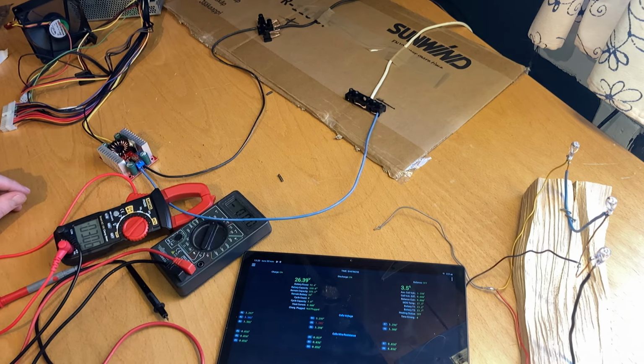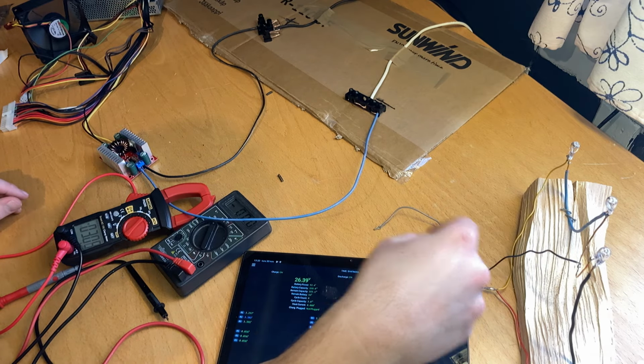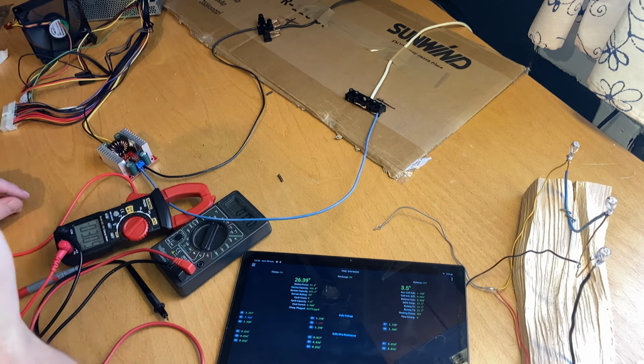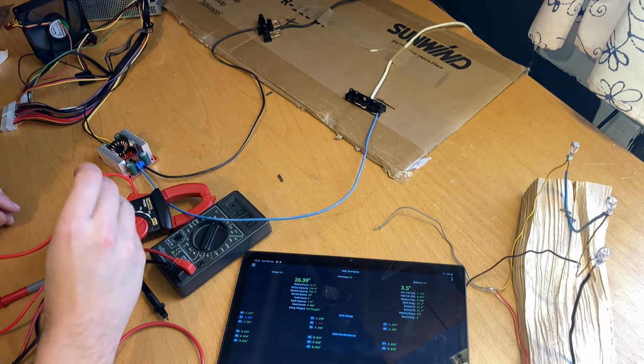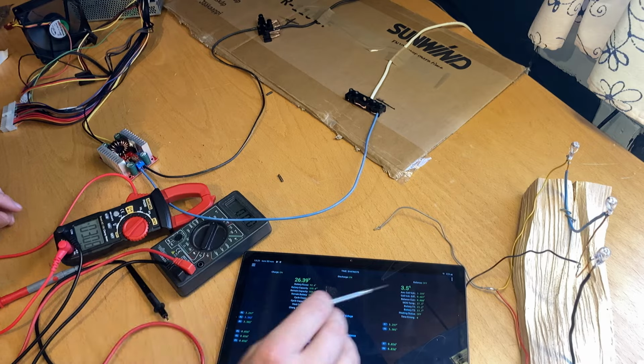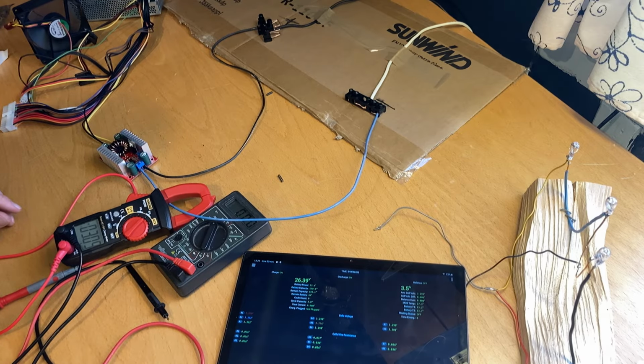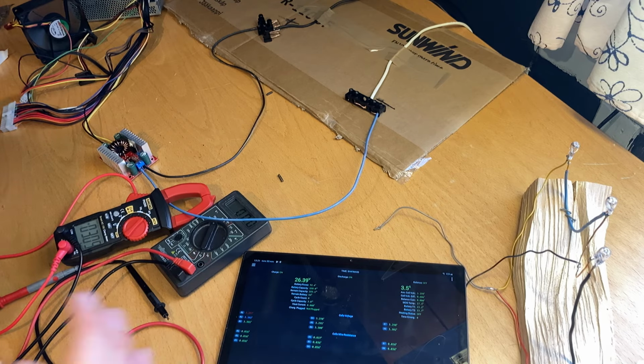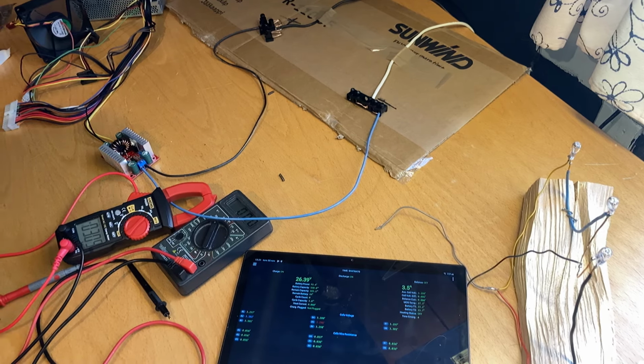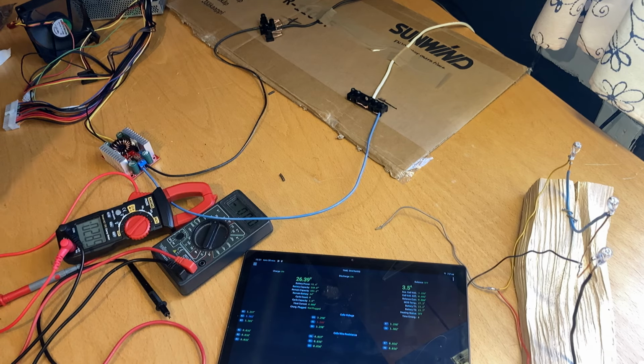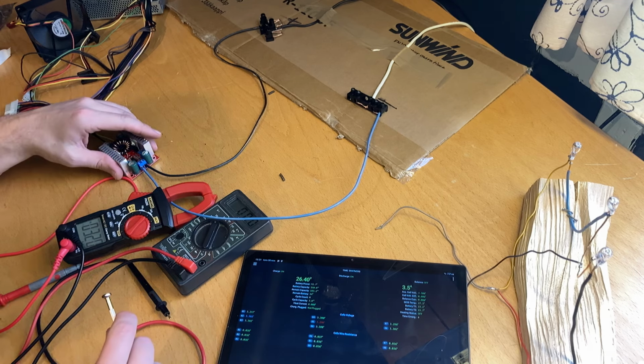You're getting 100 watts into the battery, you say. 3.5 amps there according to BMS, and 3 amps according to my meter. I'm trusting the meter a bit more than the BMS, because the BMS apparently needs to be calibrated, and to get as good a calibration as possible, the manual says you should have it under high current when doing it, and we're not going to get very high current. 15 amps is the maximum we're going to get.